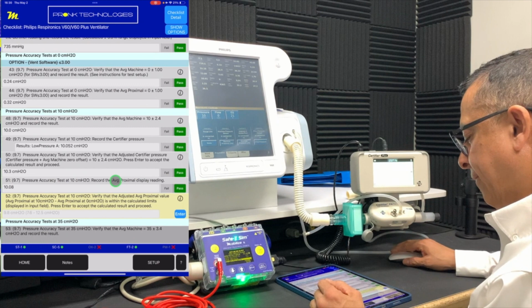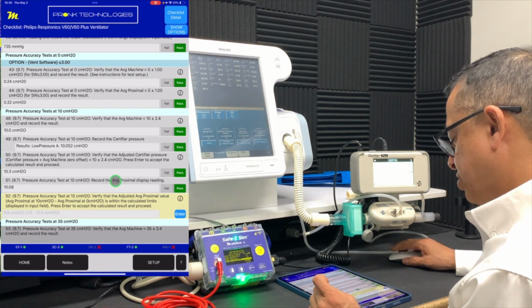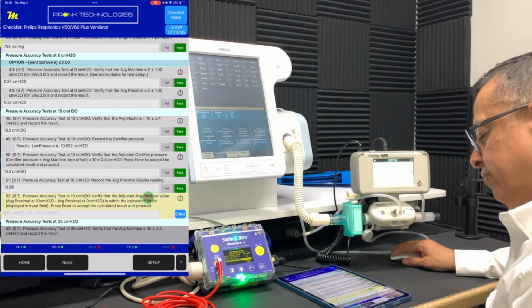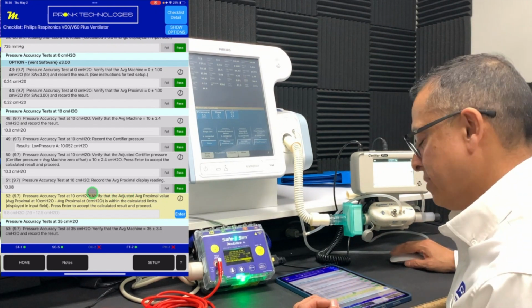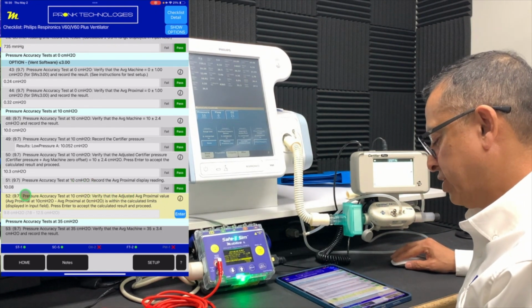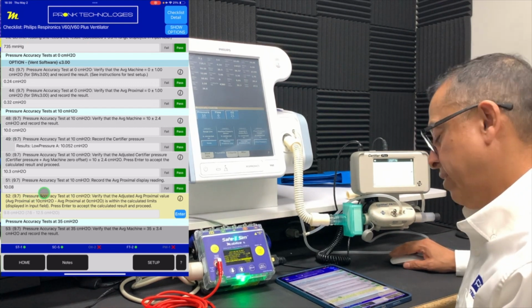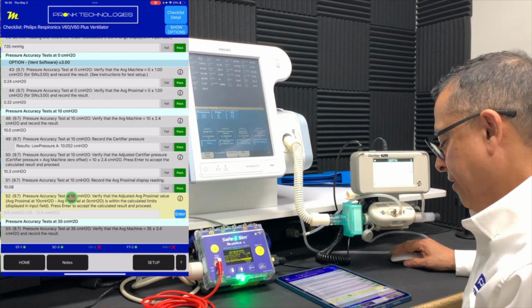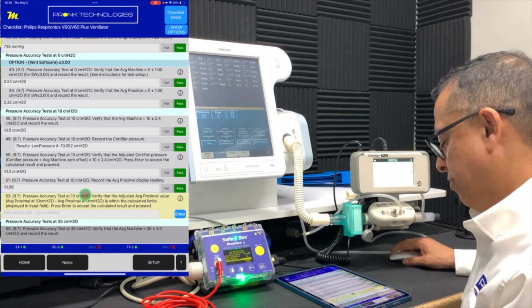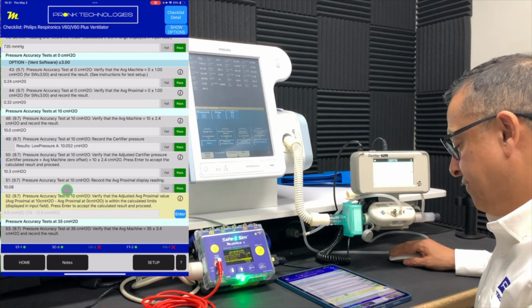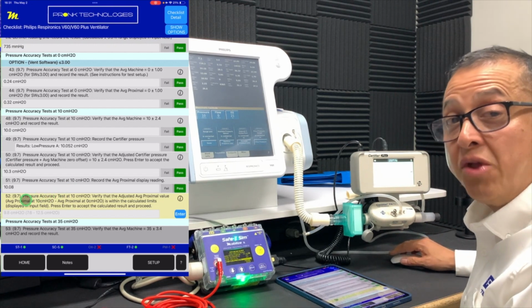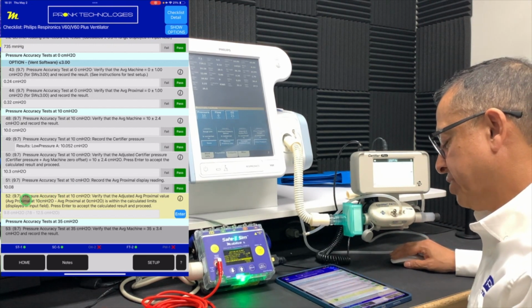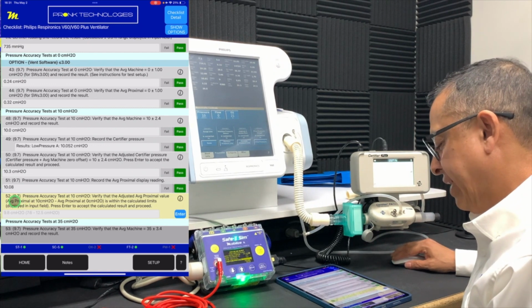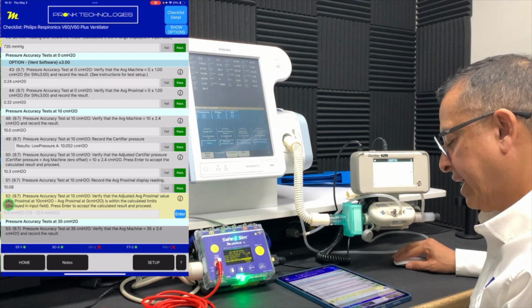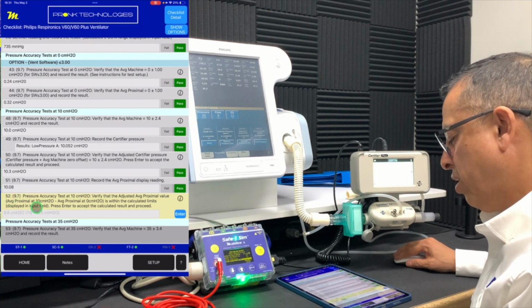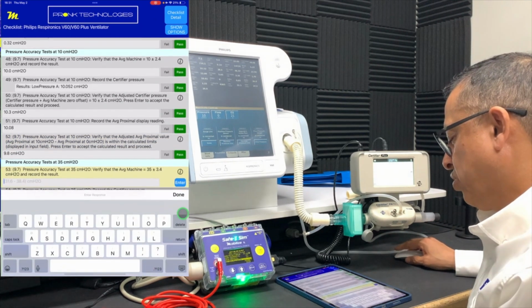Now we need to verify that the adjusted proximal pressure value is also yet another calculation. This is where you're taking the average proximal at 10 centimeters of water and subtracting from it your average proximal at 0 centimeters of water. This gives us a calculation that you normally would manually have to do, but the intelligent checklist we have here does that legwork for us. So you can see here that is a calculation of 9.8 centimeters of water, which is within range. That result is a pass.